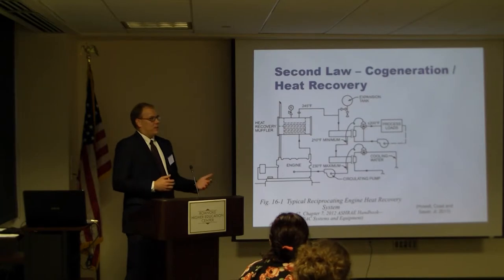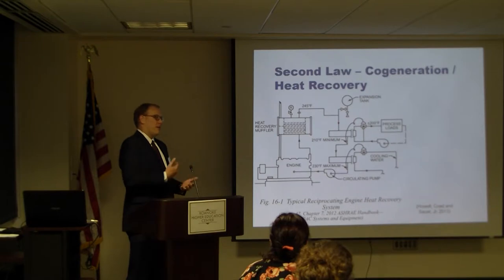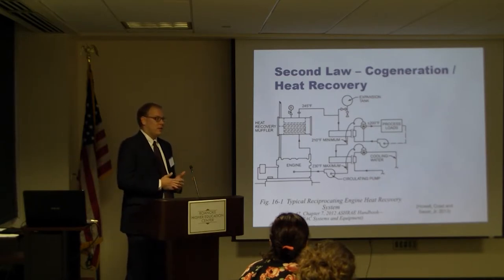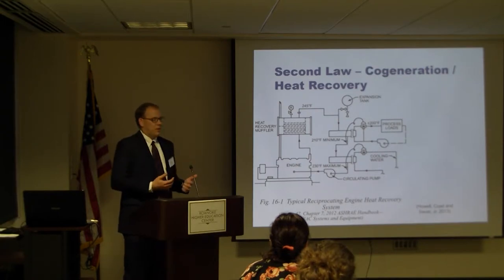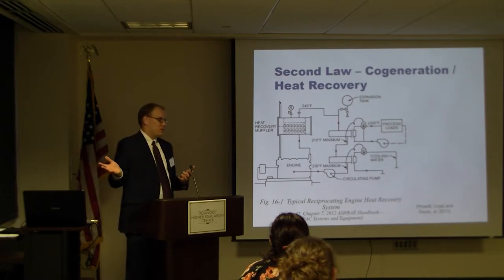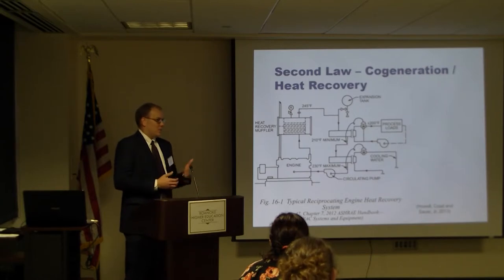One of the things we look at doing is using an electricity generator and recovering heat off of it. For example, in a data center, sometimes it can be very advantageous to run a generator all the time off natural gas, recover the heat, distribute it somewhere else, and sell that heat to somebody else, while we use all the electricity in the data center, or use the electricity to generate cooling. There are a lot of different approaches we can take with cogeneration to recover the energy we're generating in one place and put it to use somewhere else, as opposed to it being wasted up a stack, rejected to a radiator, or anything else like that.